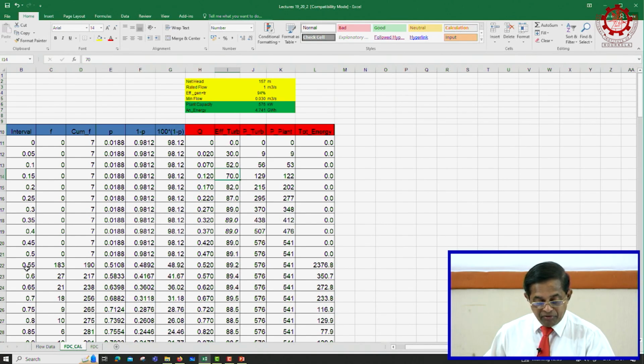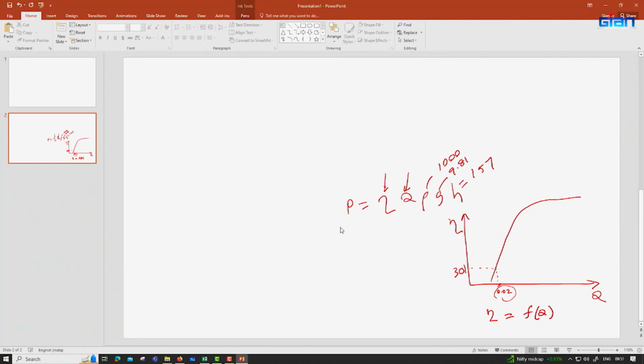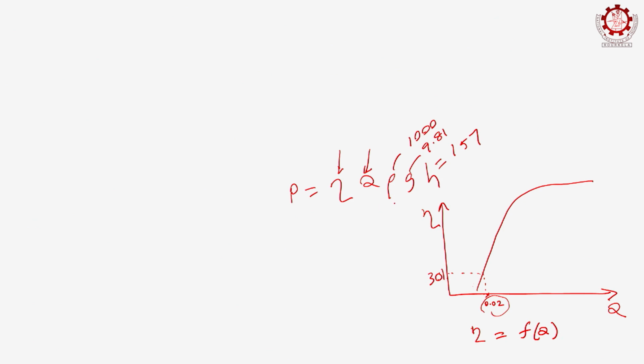And you can see at 0.55, where the most number of days, 183 days, the flow is in this range, the efficiency is 89.2. These things come from the efficiency curve. Now, once you know the efficiency, you can calculate P, because other things are already known.